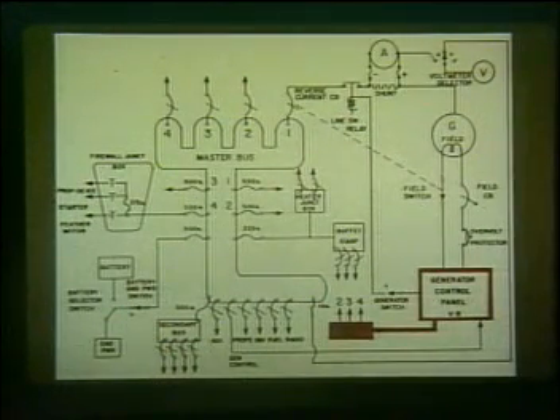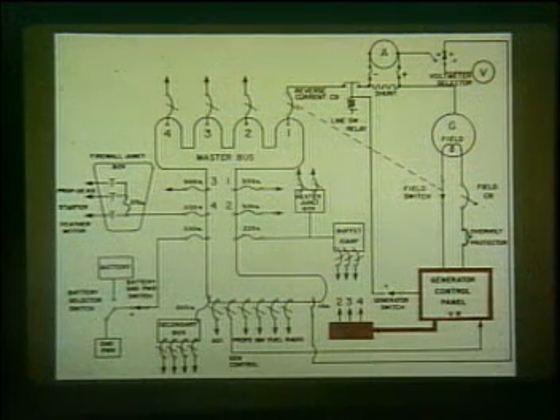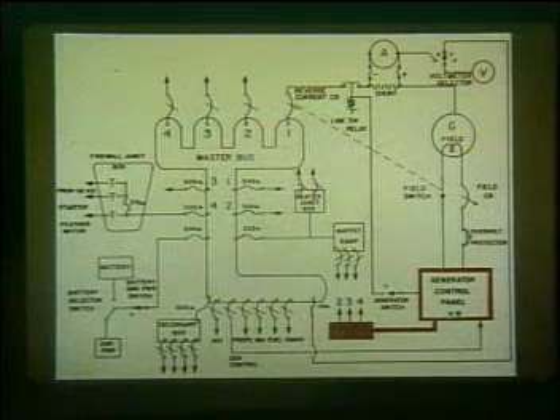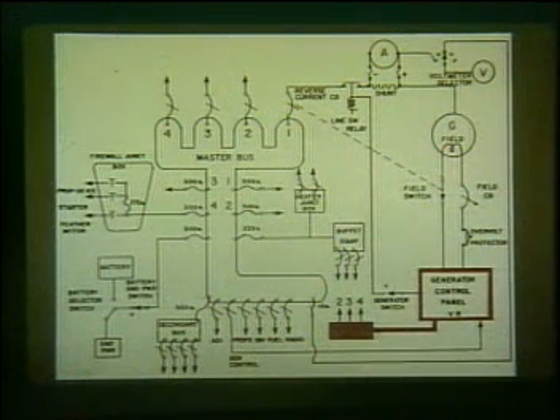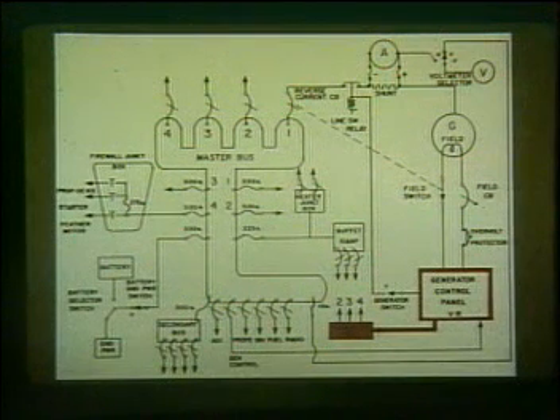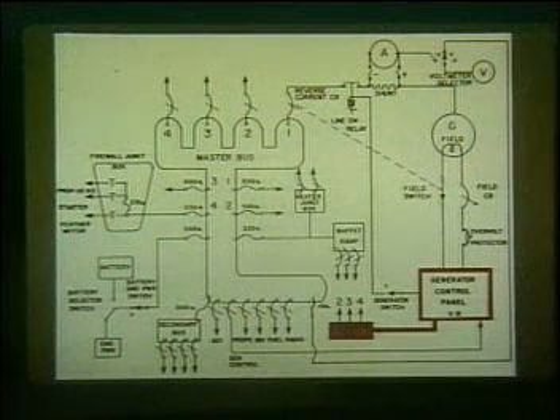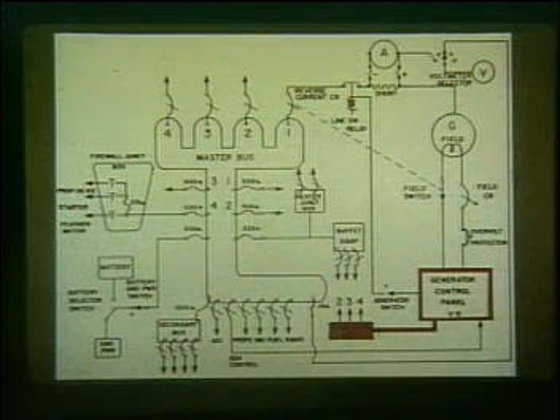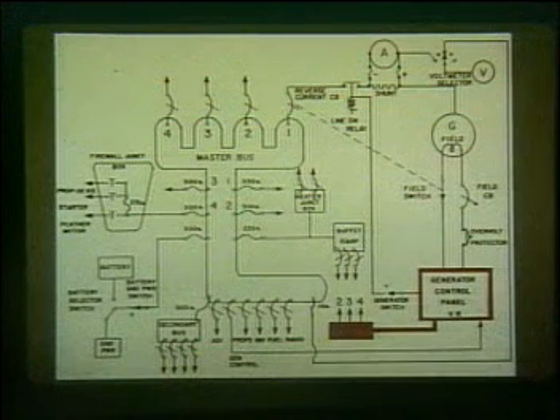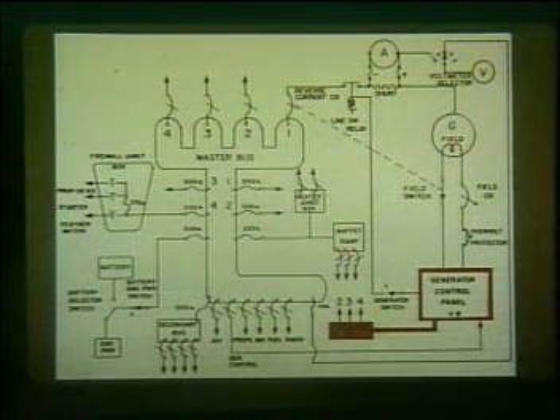To ensure an equal load distribution when more than one generator is supplying the bus, it is necessary to connect each generator control panel to a common bus called an equalizer or paralleling bus. This allows the equalizer or paralleling section of each generator control panel to compare its output voltage with the other generators, thus making adjustments to maintain equal voltage. The equalization circuit is automatically disconnected when the generator is disconnected from the master bus.